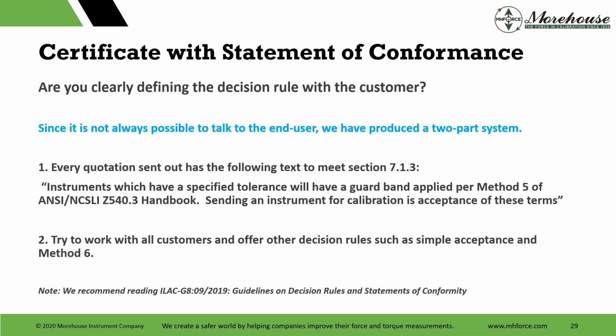They said, are you having the discussions? Did a customer agree to method 5? I say, since it is not always possible to talk to the end user, we have produced a two-part system. That's what we do. Every quotation sent out has the following text to meet section 7.1.3. Instruments which have specified tolerance will have a guard band applied per method 5 of ANSI Z540.3 handbook. Sending an instrument in for calibration is acceptance of these terms.